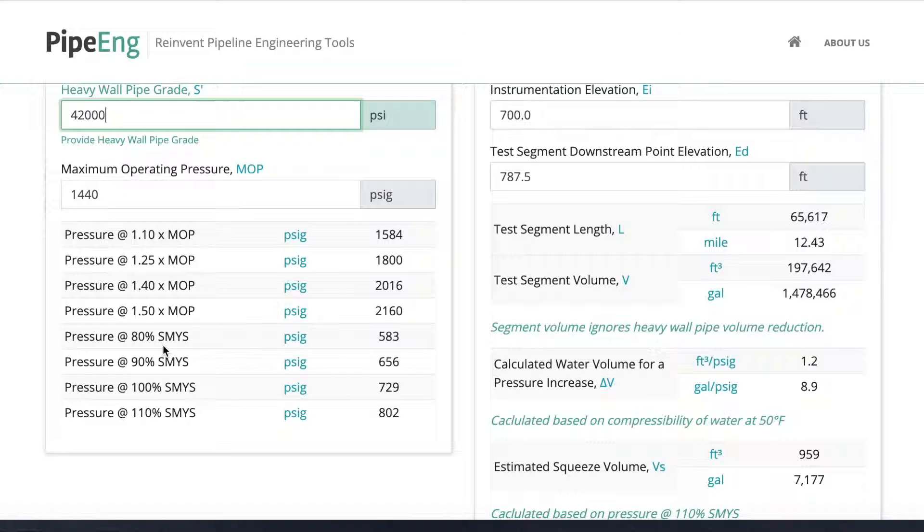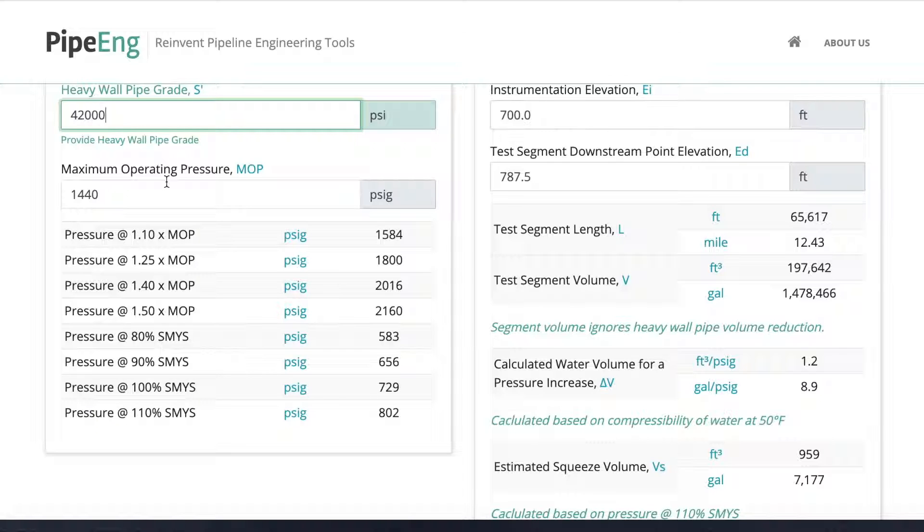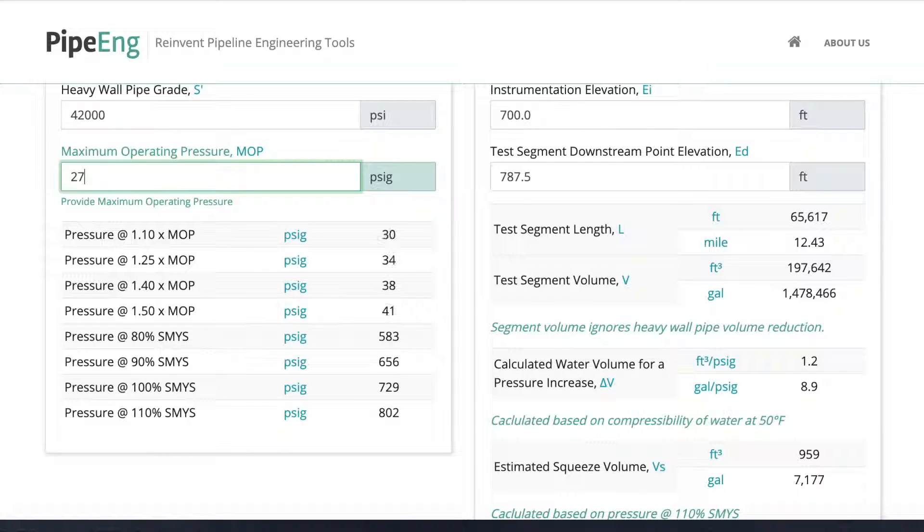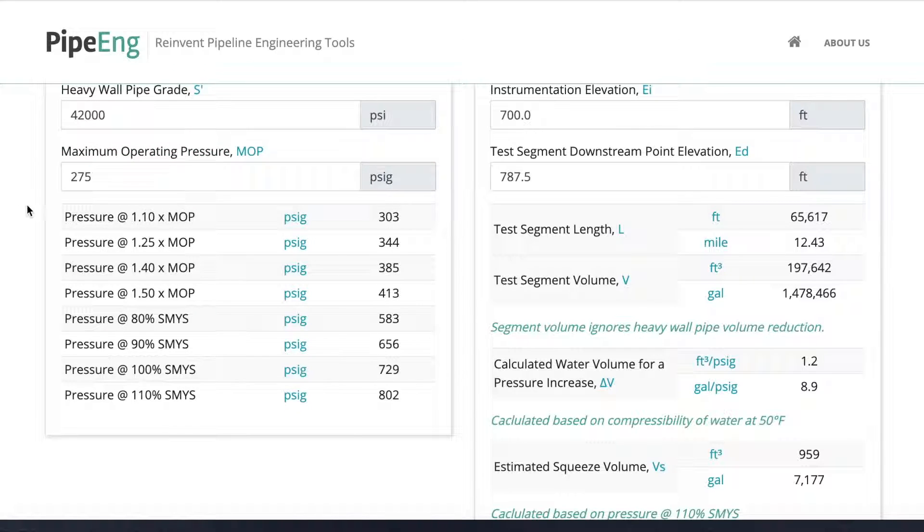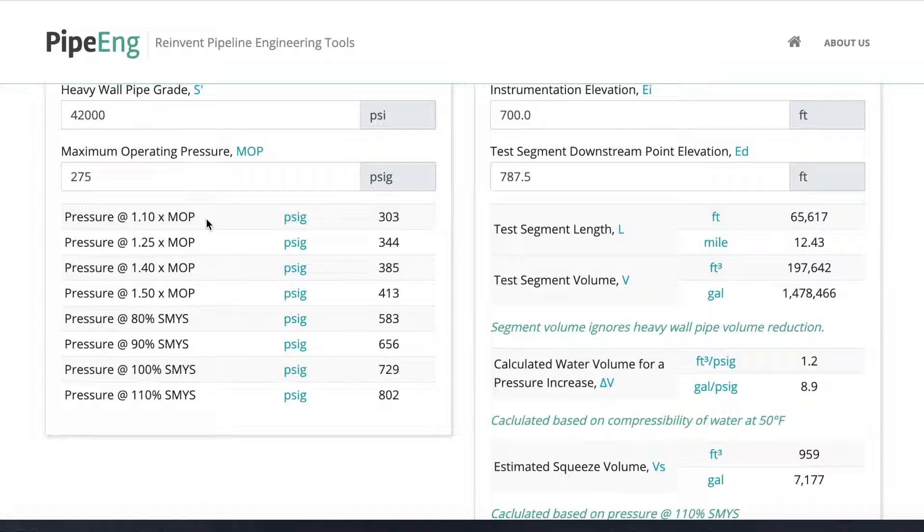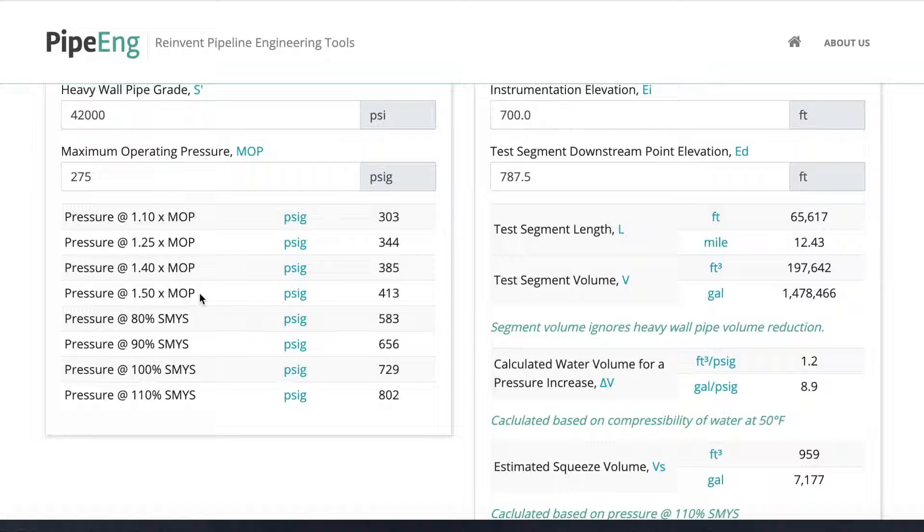The next input is very important for hydro test: maximum operating pressure. This will drive the test pressure selection, along with the pipe spec. For this example, let's assume the design pressure for the system is 275 psi. Below you can see quite a few lines to show the pressure at different conditions. For example, in the first four, we can decide what's going to be the pressure value for 110 percent MOP, which is maximum operating pressure, or 125 percent, 140 percent, or 150 percent. Usually, the minimal test pressure required for stress test or leak test is determined by percentage of MOP.